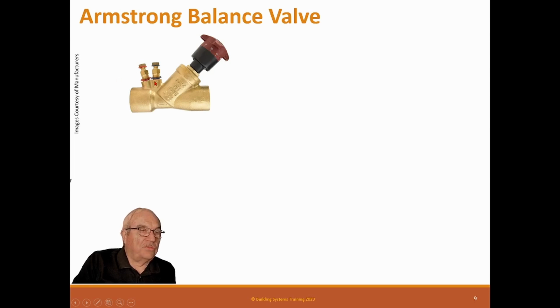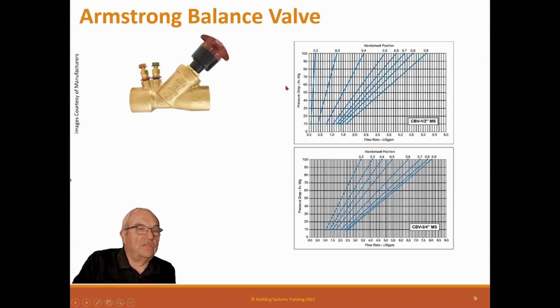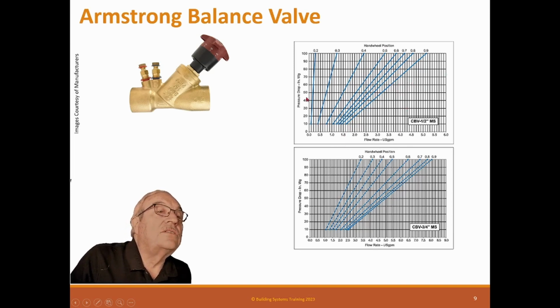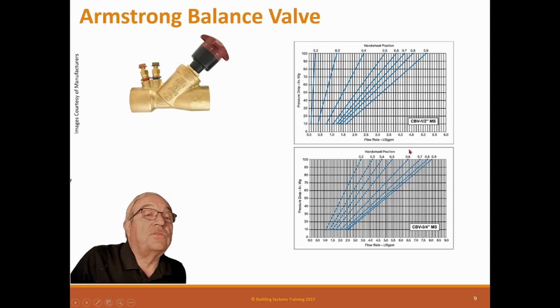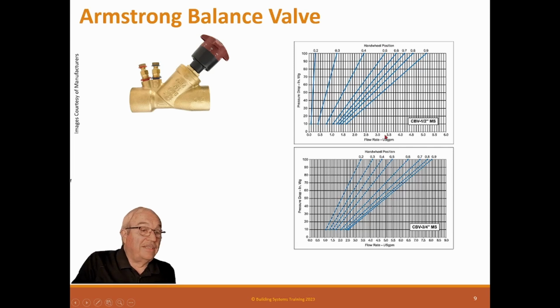And this is your orifice down here, where you're measuring flow across an orifice. And this is real simple. You've got these graphs, and you can see that this is your flow, and this is your pressure, and this is your hand wheel position. These are for a size of valve. Like this is for a 1/2 inch, this is for a 3/4 inch valve. So if you're going to set it at 0.5 and you read a pressure here, then you go over 0.5 and down to your flow. So you don't need a calculator for that. You can just look at a curve. That's all you need to do.